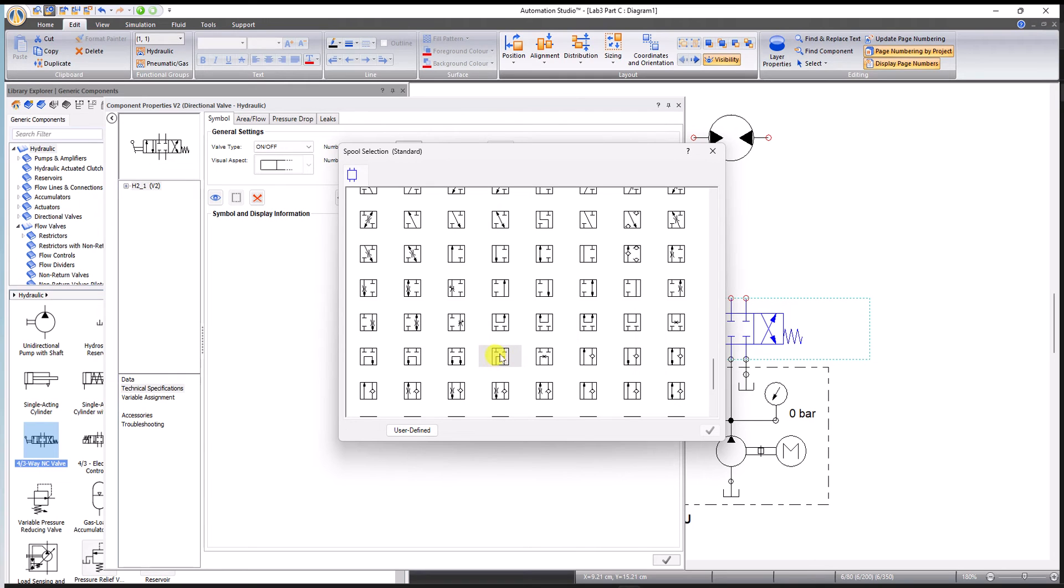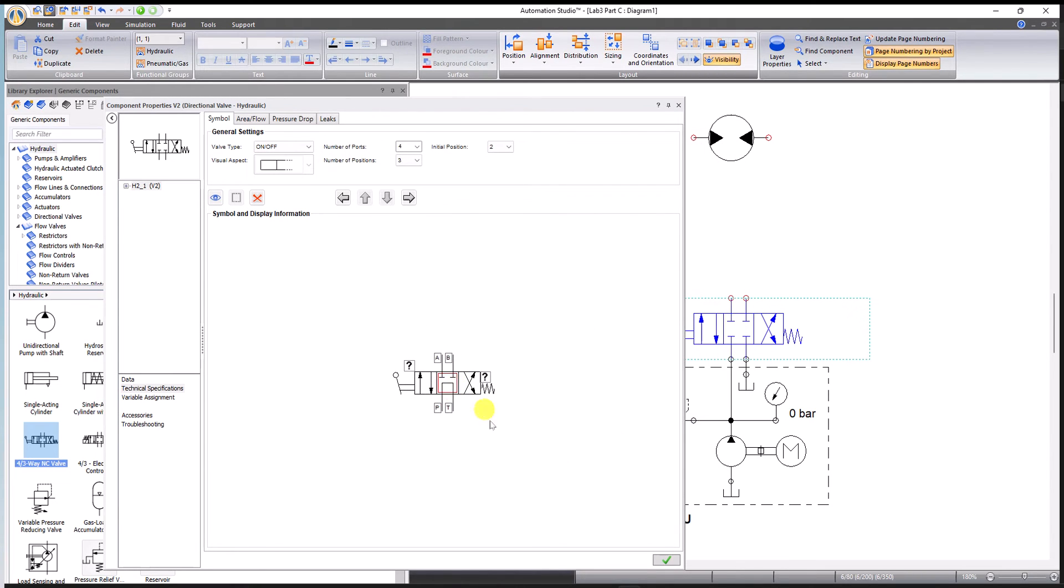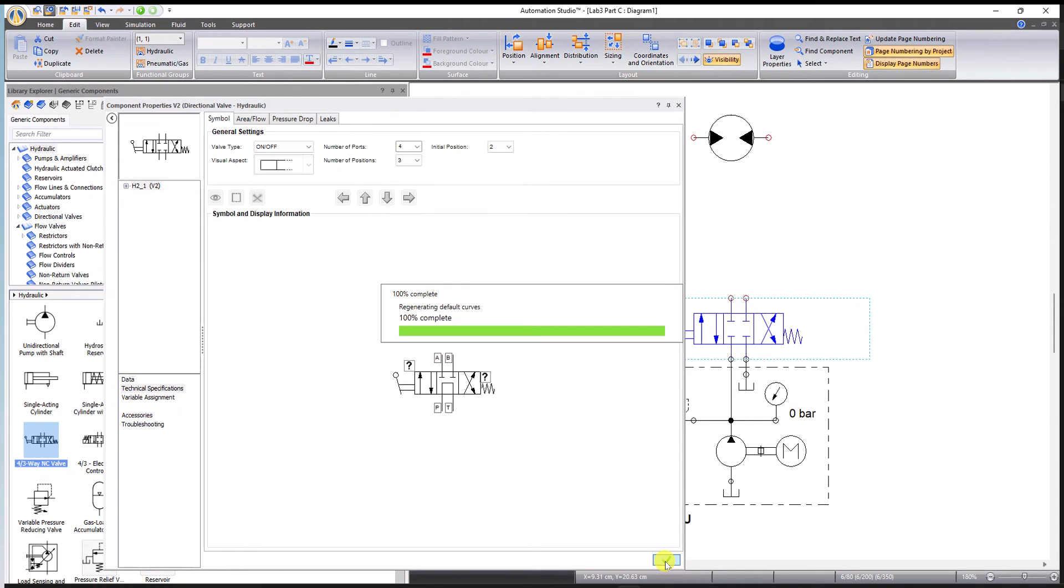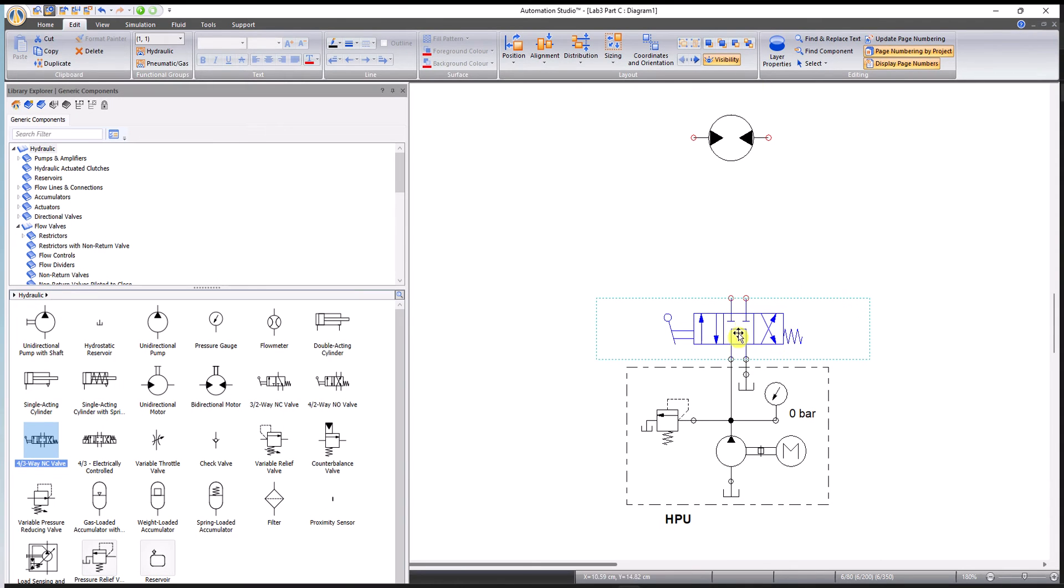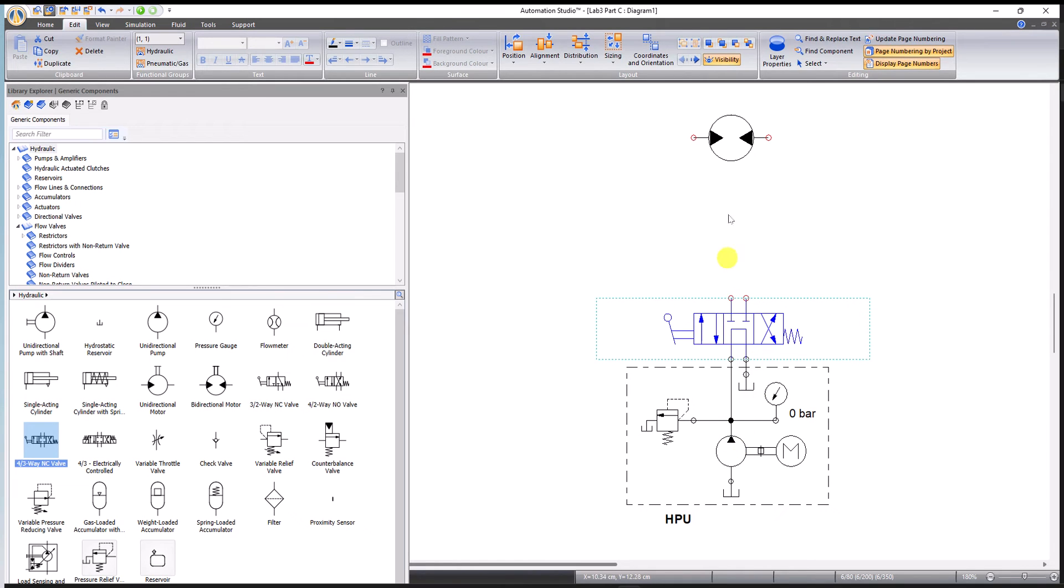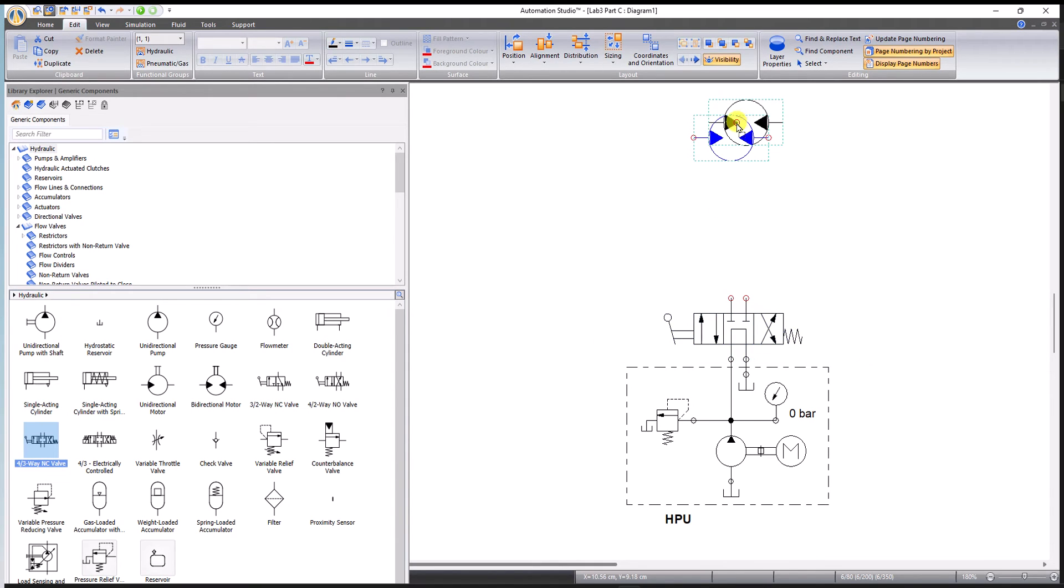The tandem configuration is down there somewhere. I'll scroll down a little bit. Here, this is the tandem where the P and T are internally connected. Select that, hit apply, and it changes to the tandem center. Now it's changed. So we have now a manual lever, motor operated 4 by 3 DCV with a tandem center.